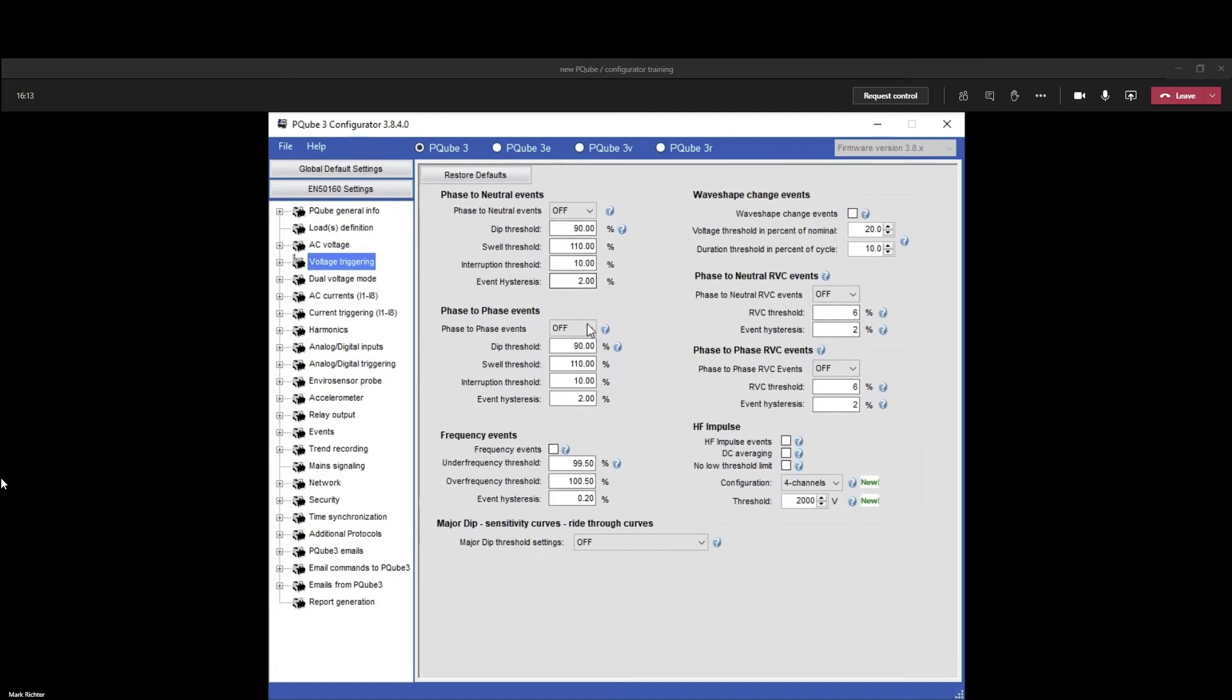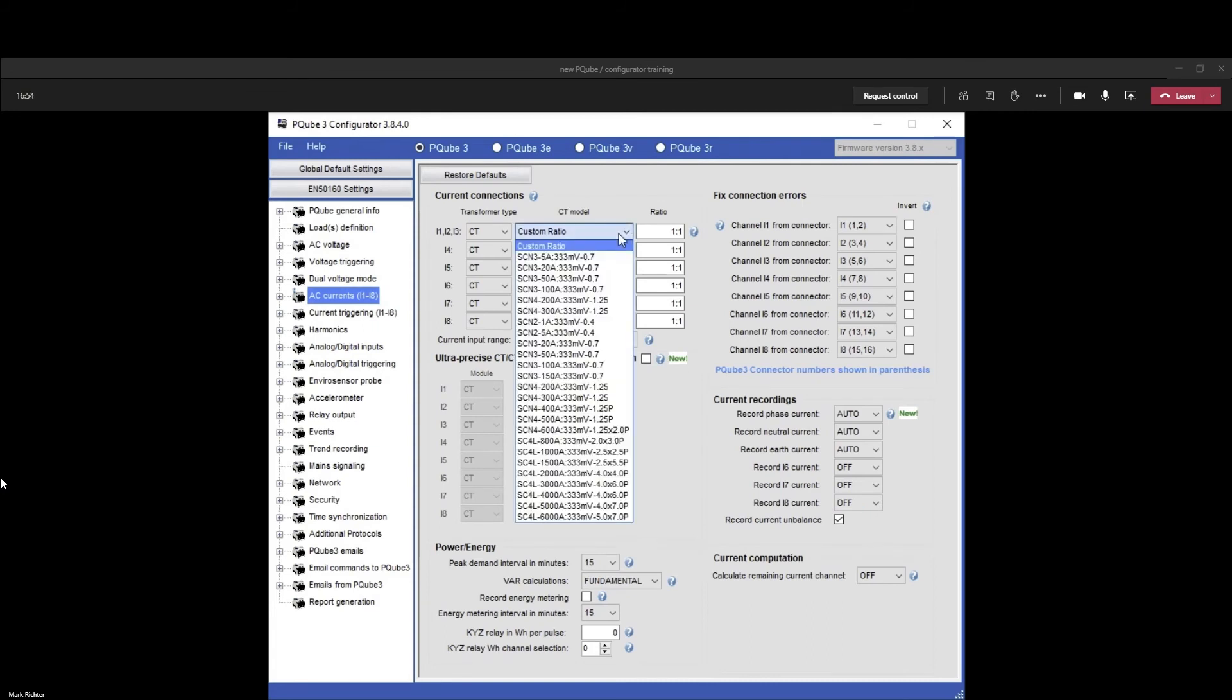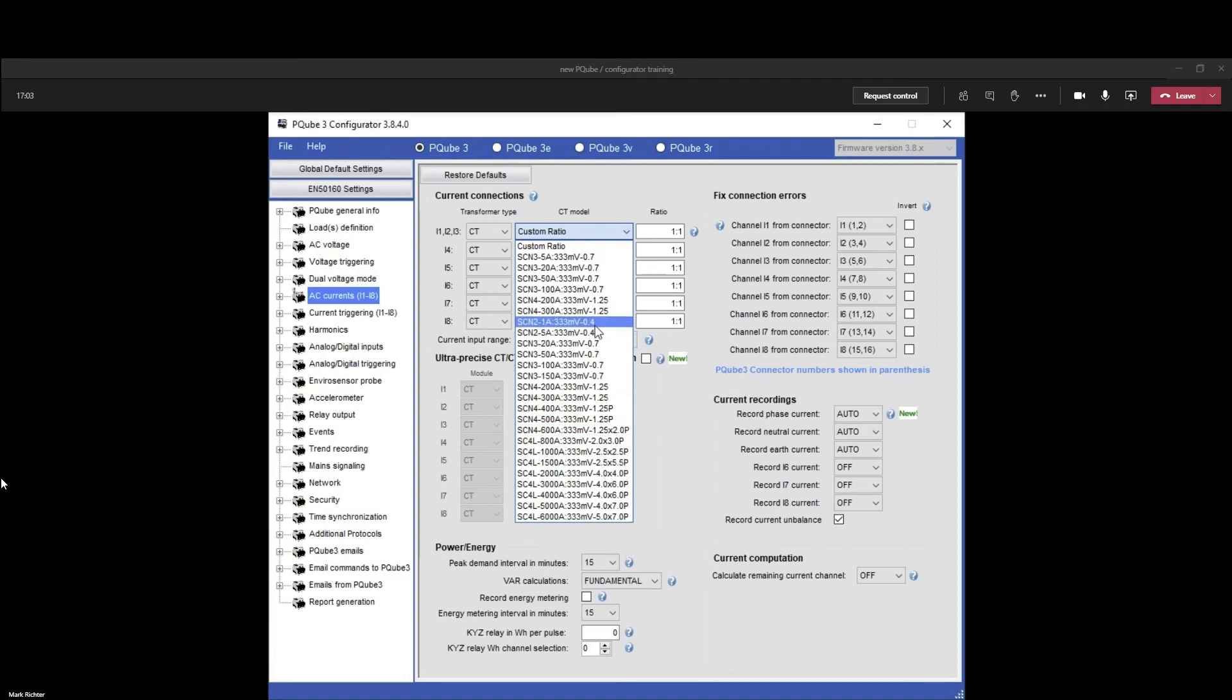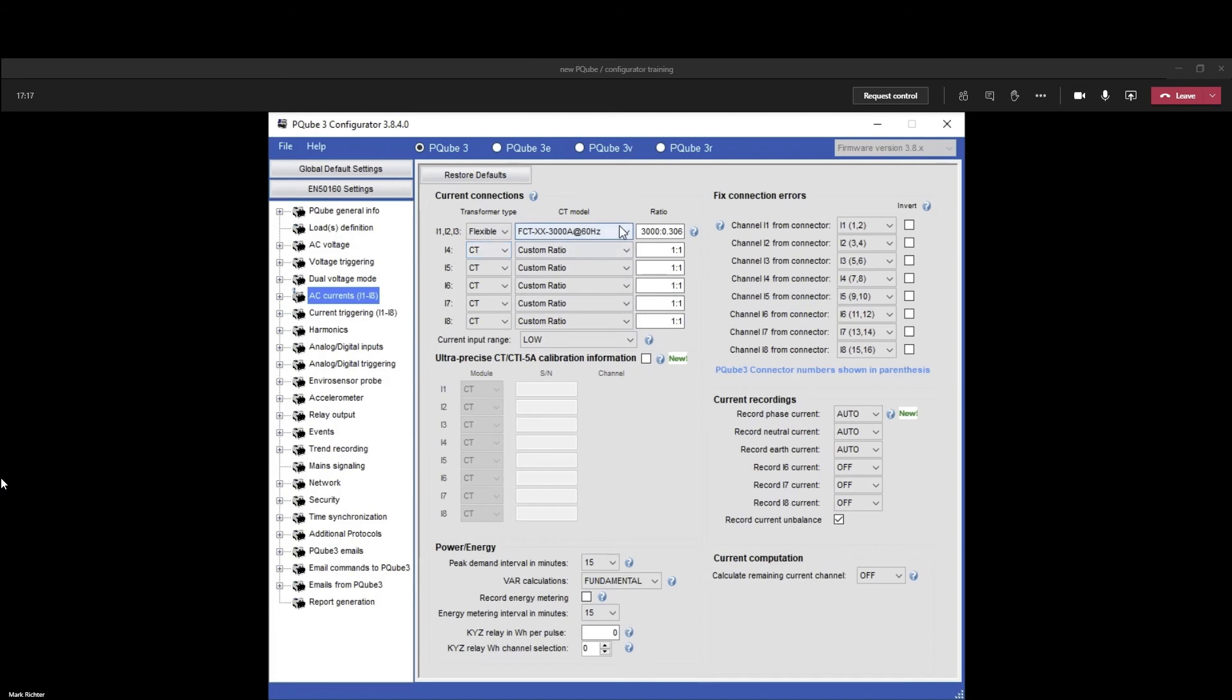On your CT for I1, I2, I3, you can pick the part number. The one I have here is an SCN2. That's it; my ratio is configured for this CT. There are occasions where you have a Rogowski coil. If you do, you must change this to flexible and then check your flexible CT.